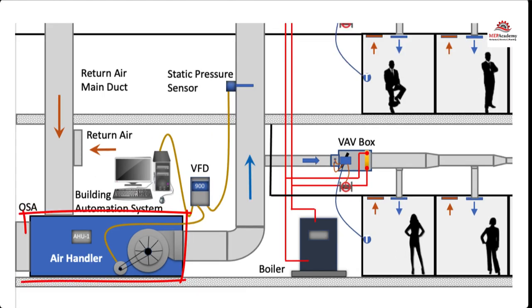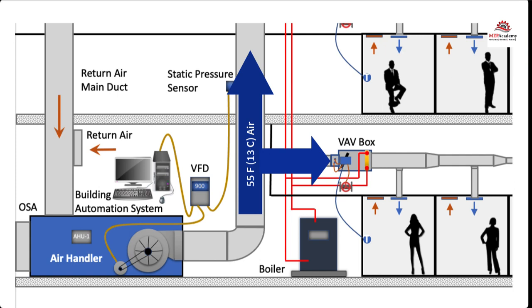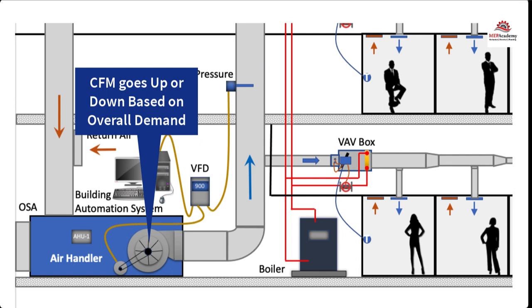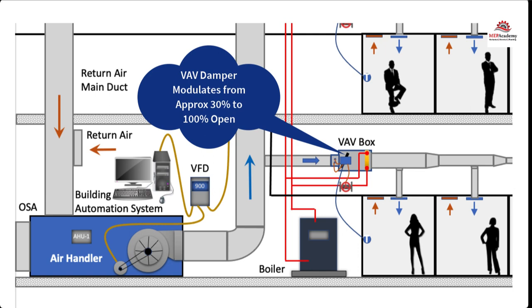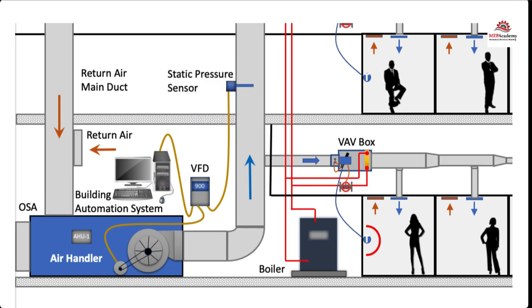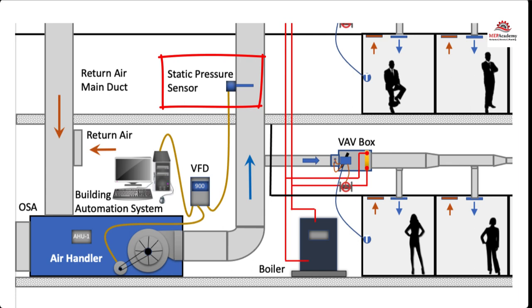The air handler will deliver a constant temperature of 55 degrees Fahrenheit or 13 degrees Celsius supply air to the VAV boxes. While the supply air temperature stays constant, the volume CFM of air will vary based on the total demand of all the zones on the system. There are several control strategies to adjust the speed of the fan which we'll discuss later. As the VAV boxes open or close their damper due to demand called for by the temperature sensor in the space, the pressure in the main supply air duct will either increase or decrease. This pressure change is picked up by a static pressure sensor in the main supply air duct.